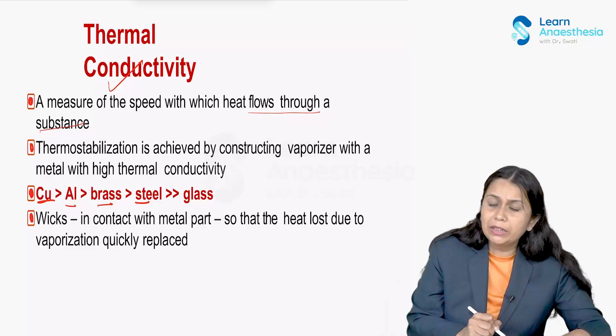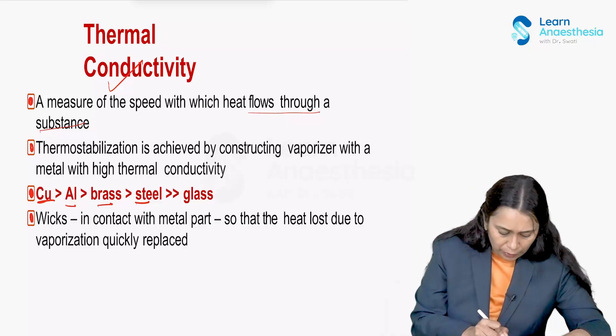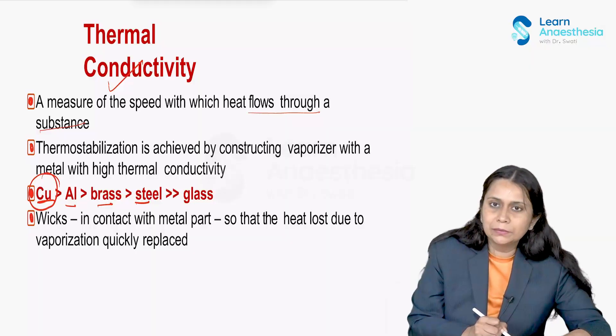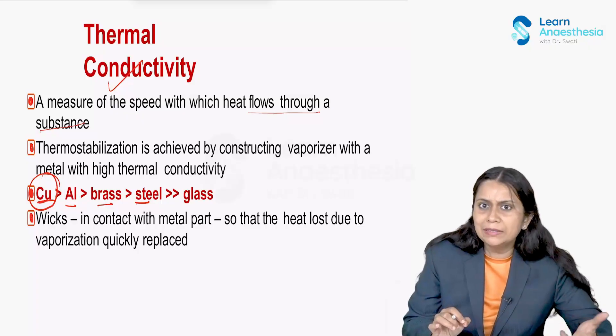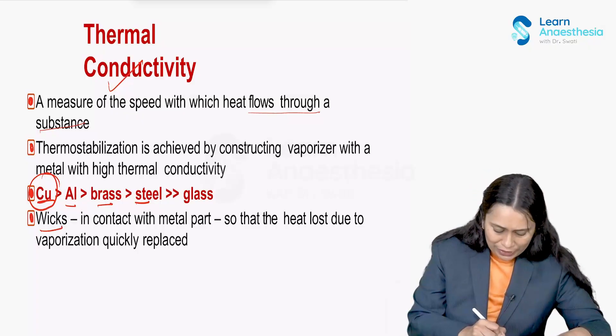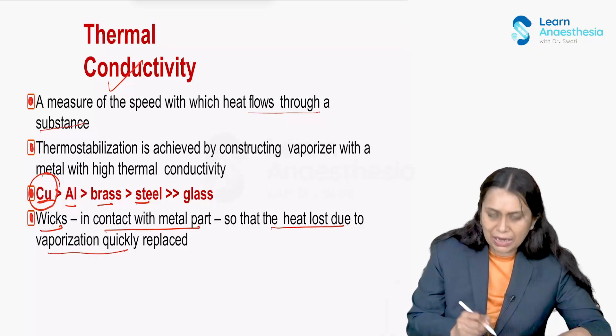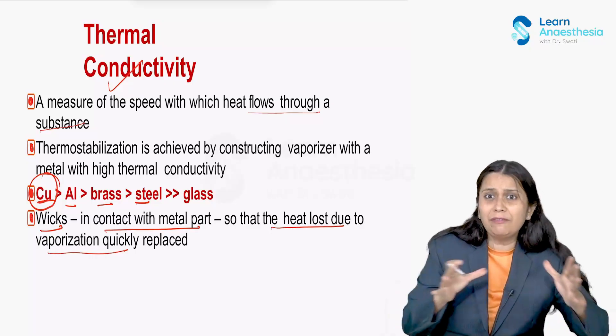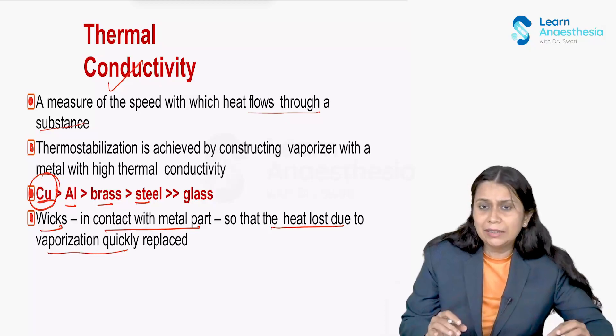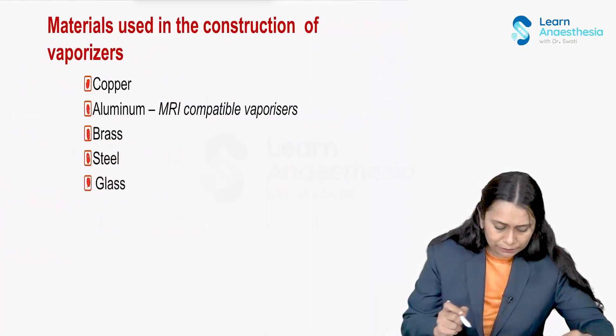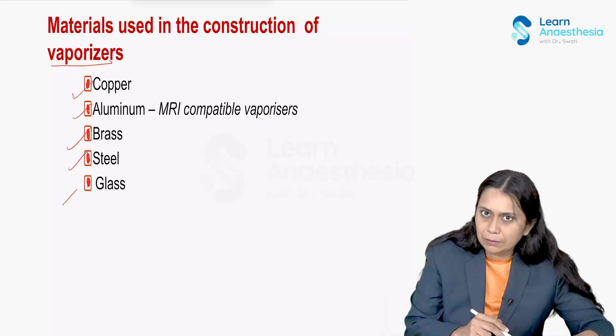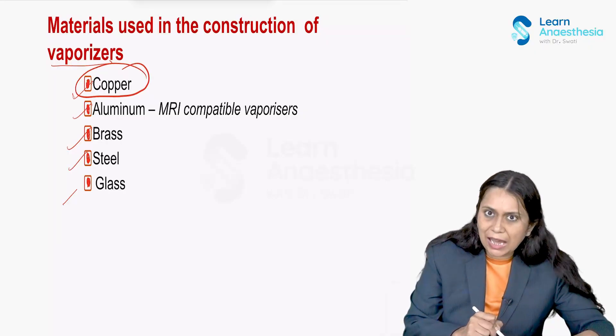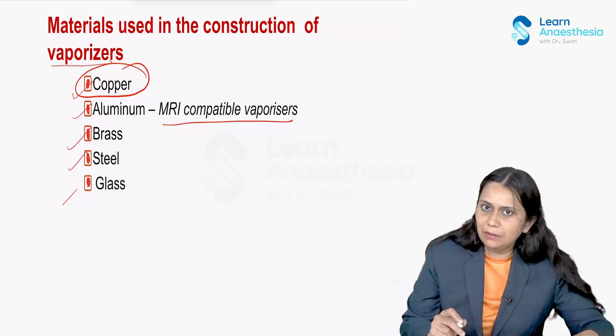Previously, vaporizers were made of glass and steel. Today, most vaporizers are made of copper. Not only the metal — we also have wicks surrounding the metal which compensate for heat loss. Wicks in contact with the metal allow the heat lost due to vaporization to be quickly replaced, though this is a finite replacement. Materials used for construction of the vaporizer include copper, aluminium, brass, steel, and glass. Copper is nowadays most commonly used; aluminium is used for MRI-compatible vaporizers.